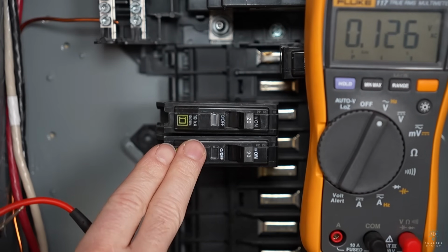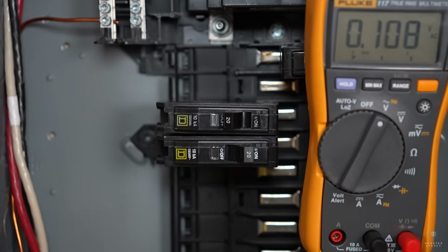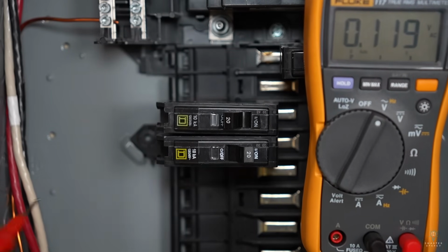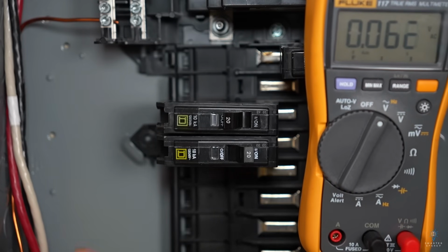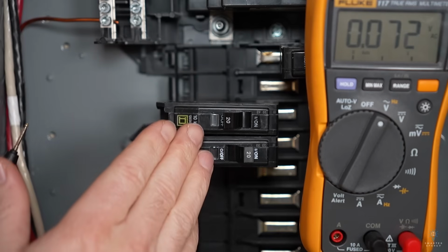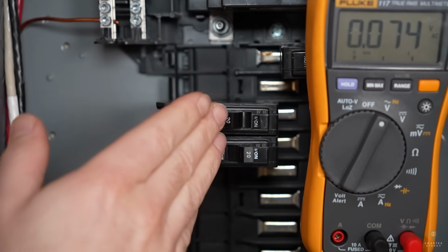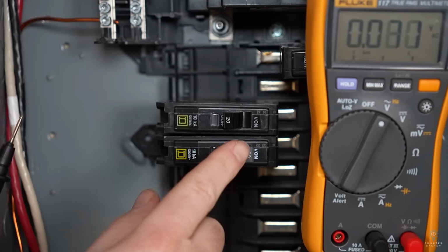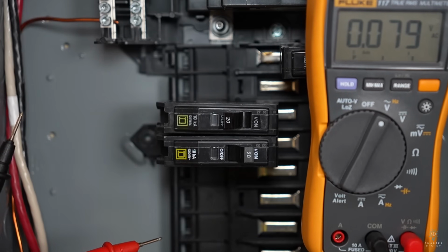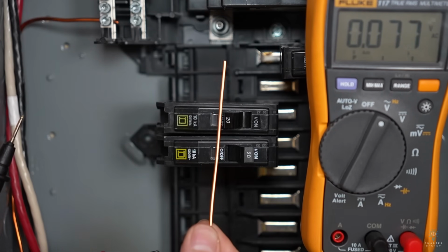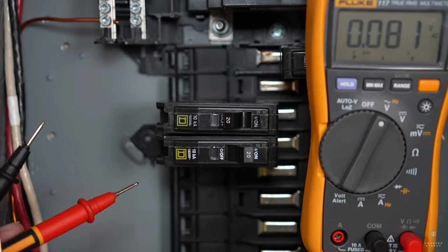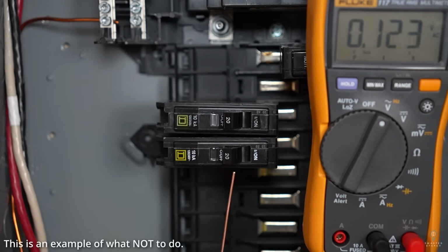But this isn't safe, because if one line were to trip, the other line may not trip, especially in those loads that might also include a neutral. For loads that tap off of multiple lines within an electrical panel, both lines have to trip at the same time. So you're probably saying, well, Dustin, could we just install a piece of wire between the 2 circuit breakers, right? Could we just do this?